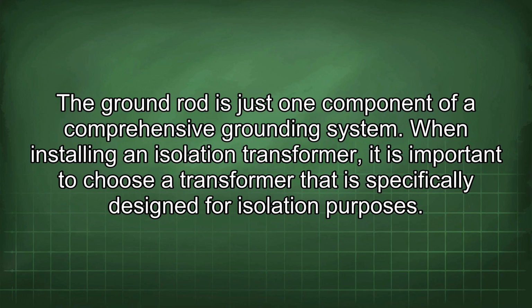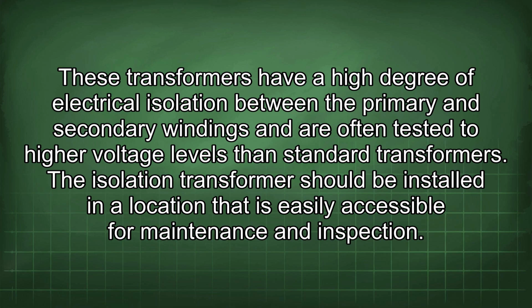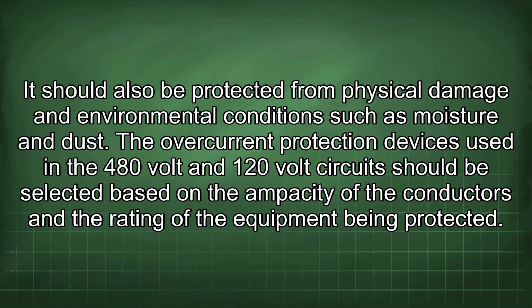When installing an isolation transformer, it is important to choose a transformer that is specifically designed for isolation purposes. These transformers have a high degree of electrical isolation between the primary and secondary windings and are often tested to higher voltage levels than standard transformers. The isolation transformer should be installed in a location that is easily accessible for maintenance and inspection. It should also be protected from physical damage and environmental conditions such as moisture and dust.